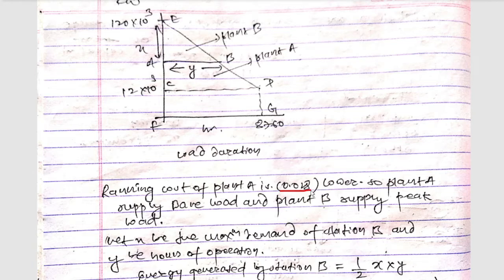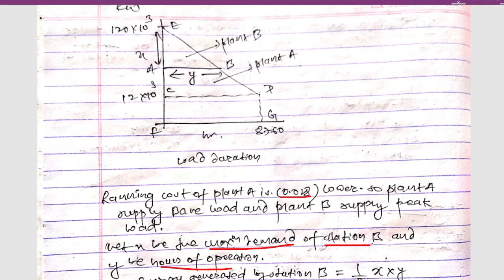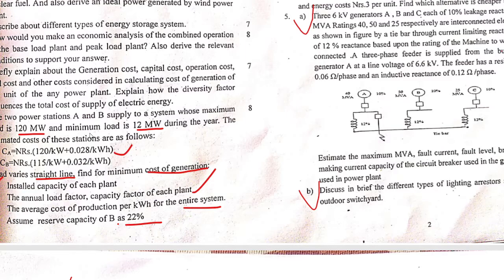Since the running cost of plant A is 0.028 per kWh, which is lower than plant B, plant A will supply the base load and plant B will supply the peak load. Let X be the maximum demand of station B and Y be the hours of operation. The maximum demand is 120 × 10³ kW and the minimum load is 12 × 10³ kW.